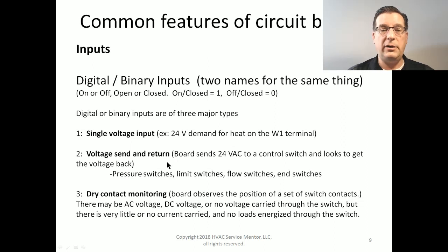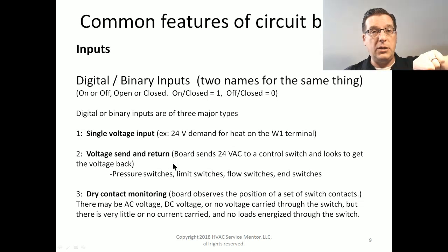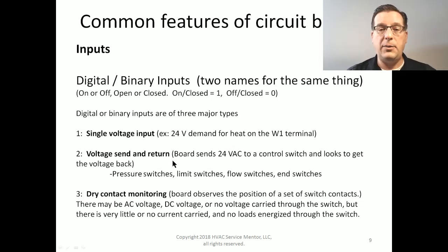Another type of input is called a send and return. In this case, the control board sends 24 volts out through a safety switch or a control switch of some kind and looks to receive the voltage back. Voltage send and returns happen somewhere in the middle of the sequence of operations, okay? So the single voltage input begins the sequence of operations. That's your command: hey, start doing your thing. And as it begins to do its thing, it's going to have one or more send and return sequences where it sends 24 volts out from the board, usually coming out of a wire on a Molex plug, going through a limit switch or a series of limit switches or a pressure switch, and then coming back to the control board. And the control board is going to wait to see that voltage come back before it can operate. Examples include pressure switches, limit switches, flow switches, end switches, things like that.